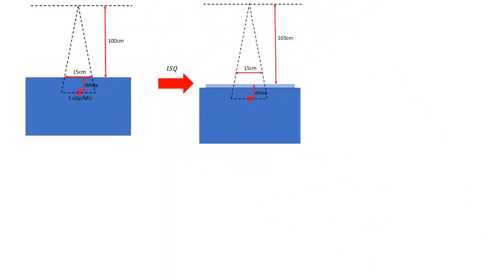We can apply our inverse square correction here by adding in our bolus and moving to the new SSD. And just keep in mind that the inverse square factor uses the virtual SSD. So when we actually go to do the inverse square, we have to use that formalism.